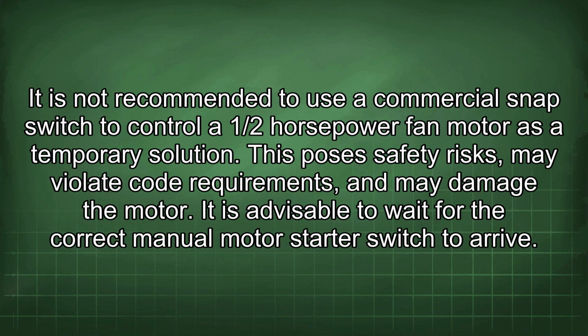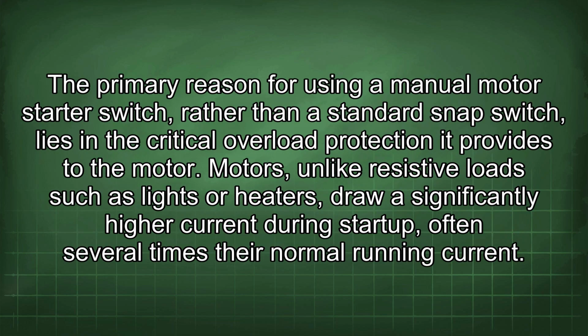It is not recommended to use a commercial snap switch to control a 1/2 horsepower fan motor as a temporary solution. This poses safety risks, may violate code requirements, and may damage the motor. It is advisable to wait for the correct manual motor starter switch to arrive. The primary reason for using a manual motor starter switch rather than a standard snap switch lies in the critical overload protection it provides to the motor.